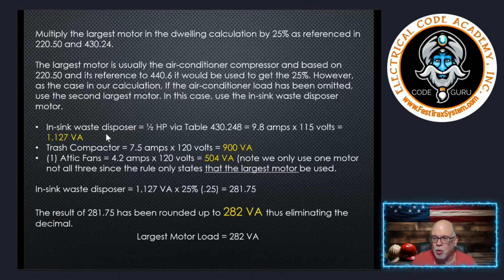And again, people say, well, why did we not use the AC? Because that is the largest motor, but we discounted that entire load when we did AC versus heat. So it's gone. That's why we're hunting for the next largest motor, and that's the InSinkErator waste disposal. That makes sense, I hope. And if you don't believe me, you have to have a leap of faith here. That is exactly how it works. I've been teaching this for 38 years. So we need to add that as the largest motor. I'm going to write this down here, and it's 282. And that is the largest motor.